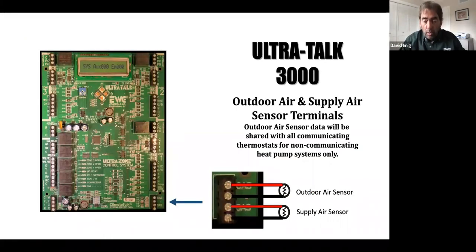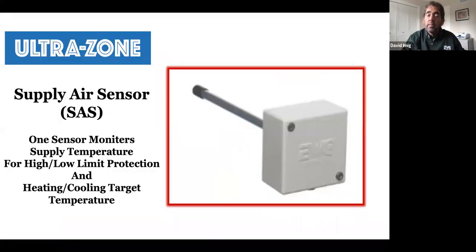And in the bottom right is where I connect my outdoor air sensor and my supply air sensor. Now, I may or may not need an outdoor air sensor. The only time I would need that is if I'm using a piece of non-communicating equipment outside, like a non-communicating heat pump. If you're using the Daikin Fit communicating, that has a built-in outdoor air sensor. I do not need to add an outdoor air sensor. The supply air sensor is a must. That comes with the panel. That's what communicates the discharge temperature and is entirely required for the operation of this product.